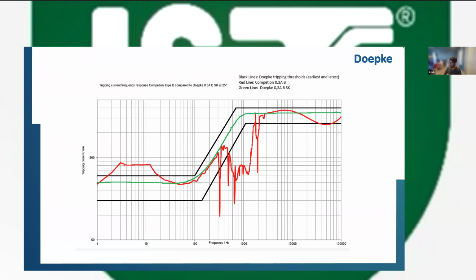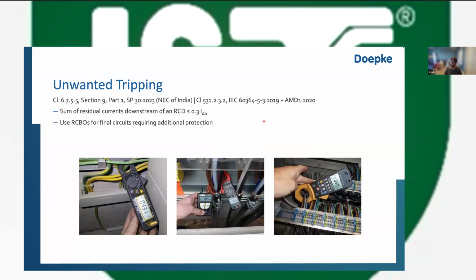Now, just a comparison, not all manufacturers are able to produce something similar. So, for example, this product can stay in the correct zone, which is the green line, but some other manufacturers, even the Type Bs, go all over the place. And this has to do with one of the most important problems reported in the field, especially from a lot of our clients in the elevator industry, which is unwanted tripping.